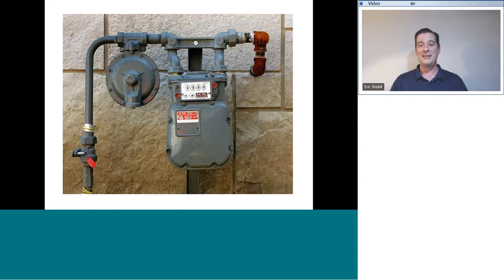It's locked. Yeah, there's a lock on it. Look to the lower left corner here, and this is the supply valve coming from the utility provider, coming from essentially what I call the street. Those gas lines are buried in the streets, and then they branch off to go to the residences. So this is the line coming from the street, and that valve is closed, and the valve is locked with a special locking fitting that the utility company provides. So either this is a brand new installation, which has not been leak tested and approved for release yet, or this is an existing installation and the customer hasn't paid their bill.